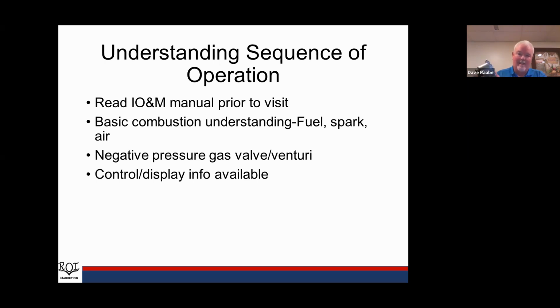And what I have is a gas valve. This lower portion is our gas valve. We have a venturi assembly, or an air inlet assembly, and this would bolt onto a blower. So we have a blower sucking air in through this opening. As it comes in, when the gas valve opens, it doesn't really let gas through. It's still holding it back. That airflow traveling across this venturi pulls the gas up in and gives us our gas mixture, which then goes up into the burner and is ignited. So that's kind of how that works. You can flip me back so you can see the presentation now.